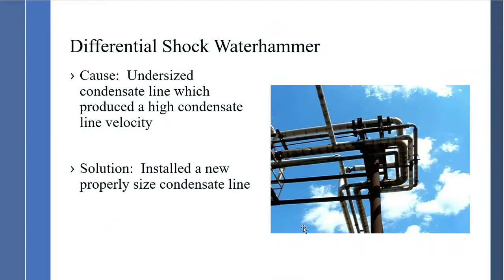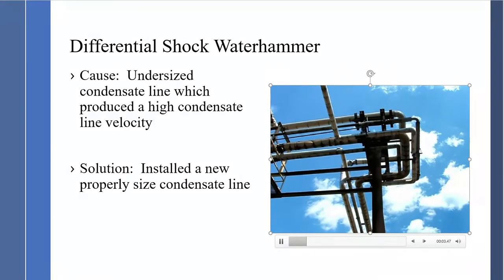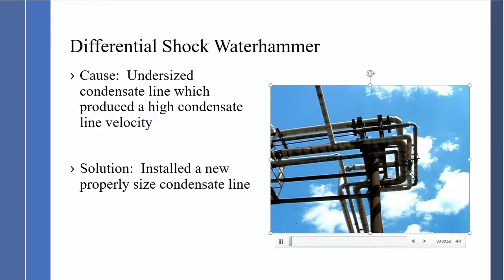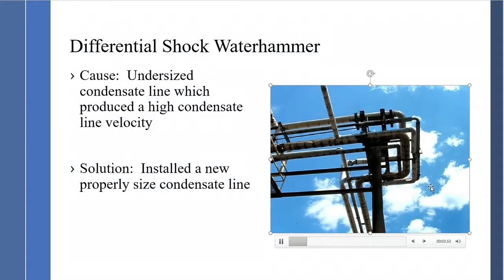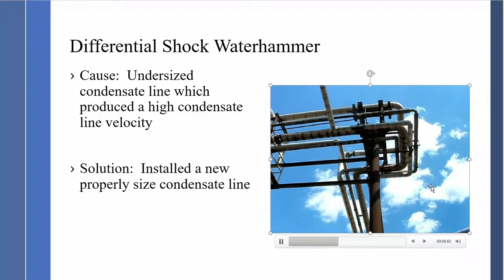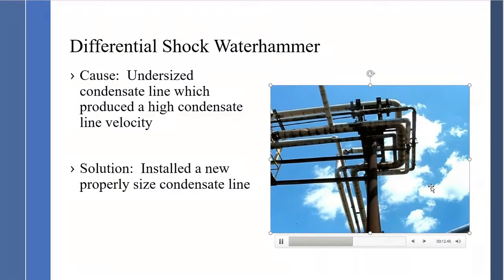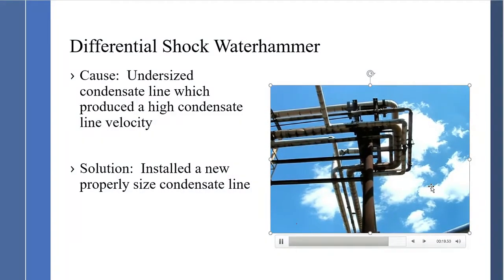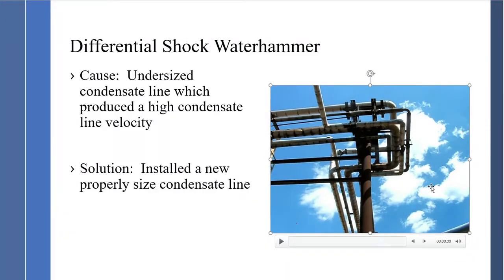Another differential shock video shows significant pipe movement. The differential shock was caused by an undersized condensate line producing high condensate line velocity, with severe reactions occurring throughout the system. In this application, a new condensate line had to be installed — properly sized, supported, and guided.